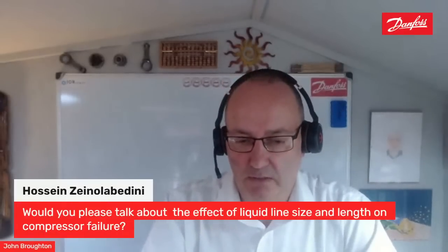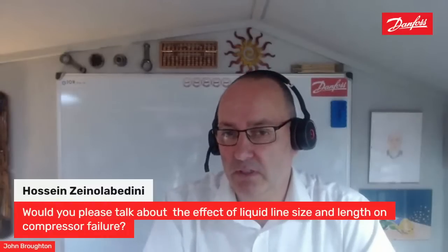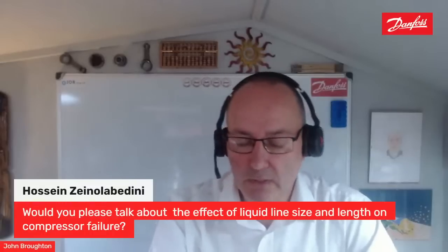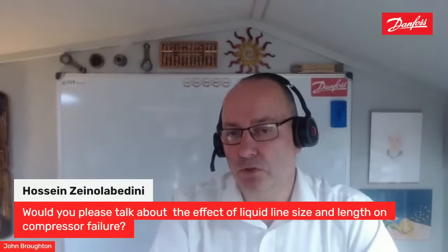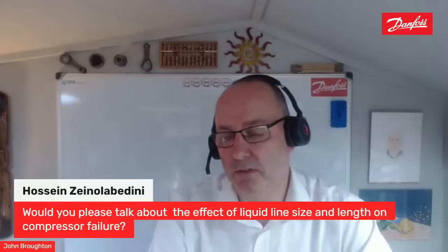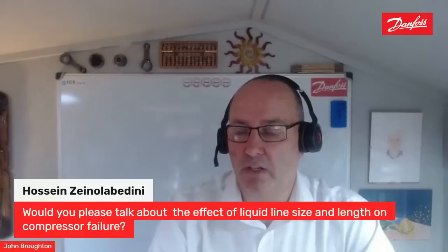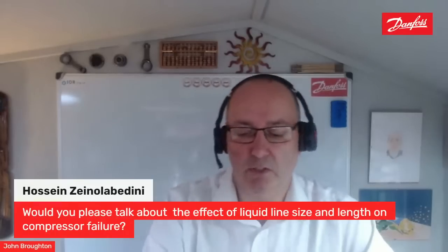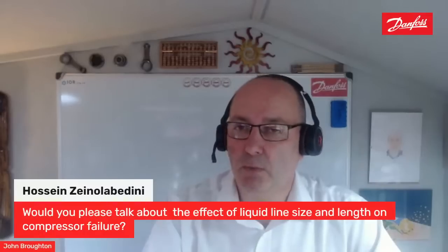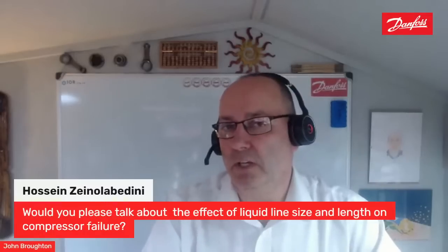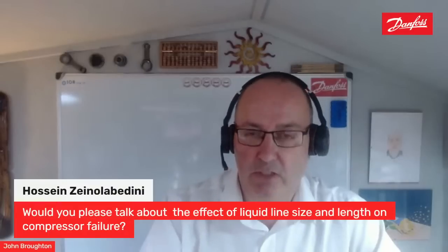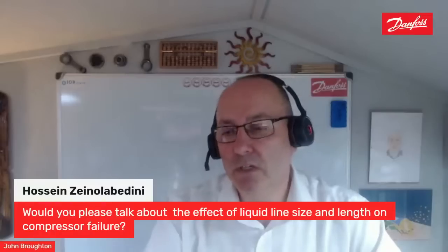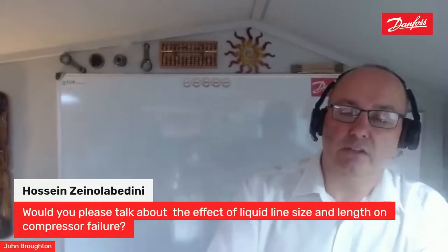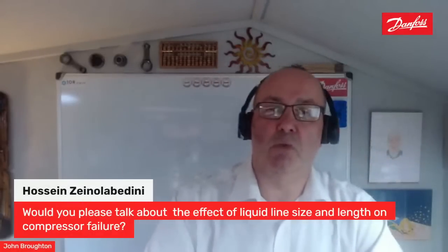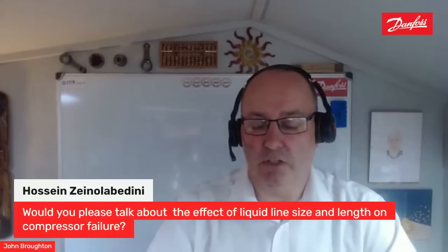The effect of a liquid line and the effect of a suction line. Now, the liquid line is there to transport liquid refrigerant to our expansion device. Most important, as we said, if it's too small, you will get noise and you won't get enough liquid to the expansion device. If it's too large, then we'll get low velocity. We'll then have a very increased charge of refrigerant. We then try and pump the system down. That refrigerant's got nowhere to go. So the liquid line size is important, but I would say the single biggest issue that I have on site is suction line size, and that's getting the correct velocity back to the compressor. And if you don't have the correct velocity, then you won't get the oil entrained in that refrigerant coming back to your machine, and the compressor will run dry of oil and eventually fail.